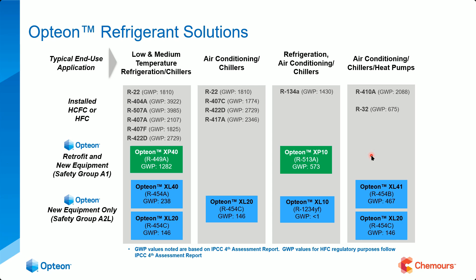Refrigerant options and key recommendations for existing 404A, R22, 407, and 507 systems: we're going to retrofit to R449A. This is a great gas. You also have the option of doing R448A. For existing 134A systems, as we talked about earlier, you're going to retrofit to 513A, Opteon XP10. This is a great refrigerant - make no bones about it, this is probably the best retrofit gas I personally have ever seen, and a lot of engineers agree with me.